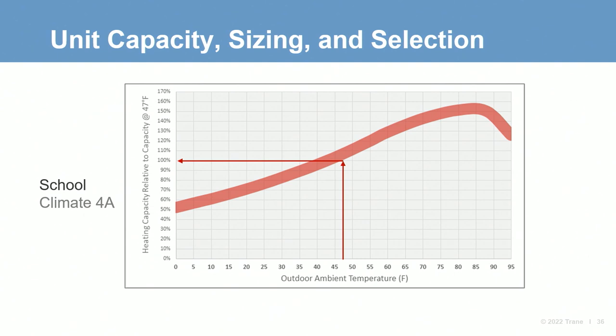This figure shows the relationship between available heat pump capacity as a function of outdoor air temperature, normalized to the 47 degree AHRI rating point. At 0 degrees, you can expect to see about a 40 to 50% reduction from rated capacity. Also worth noting here is that the selected heating water supply temperature impacts capacity as well, but in a much more limited way.